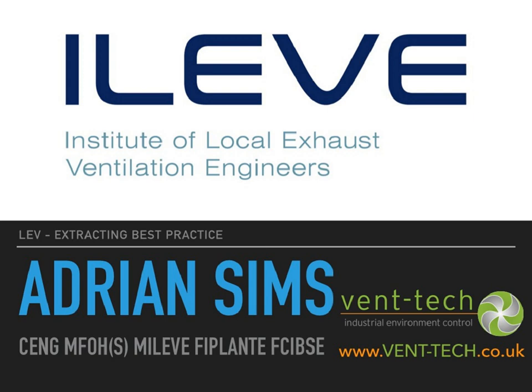If I had to work out a figure, I'd say probably 80 to 90% of systems fail. There's a couple of key reasons. One is poor purchasing—not a dig at anyone in particular, but people don't tend to understand what the LEV needs to do. They want something that sucks, and they're often sold something that moves airflow but doesn't provide adequate control. When we look at the amount of dust or fumes in the air that can cause harm—that's why I did the thing with the weighing scales—it doesn't need very much contaminant in the air to cause someone harm. A lot of LEV systems just aren't up to the job.